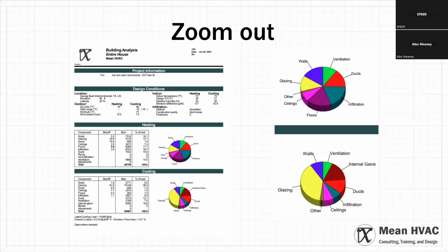But remember I was talking about humidity rises, and your encapsulated attic is a moisture trap. It's not a guarantee that it's sweating ductwork or raining ductwork, as long as we're talking about the outside, which we would be if supply and return fixed it. That's not necessarily a load problem, right? It just means that the surface of the ducts in this very cool space - those ducts aren't in 130-degree air keeping their surface nice and warm. They are going to be cold, and that is normal.